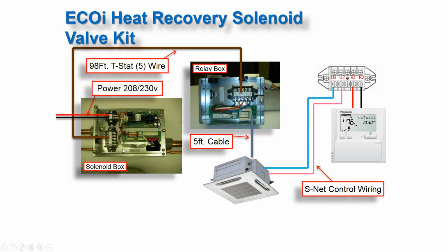Okay, all of our solenoid valve kit boxes come with a relay box for electrical and communication. So we want to install our relay boxes close to our indoor units, because our connection from the relay box to the indoor unit is only a 5-foot cable. So we can wire from our solenoid valve box, our 5-wire thermostat wire. We have 98 feet to play with, wire to our relay box, and then from there we're all set up and we can wire to our thermostat.